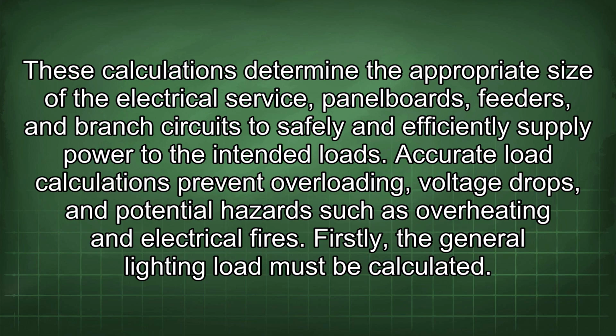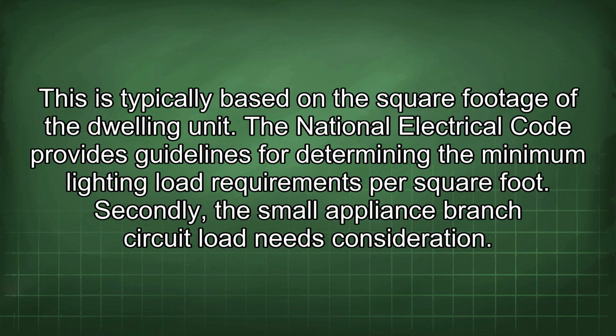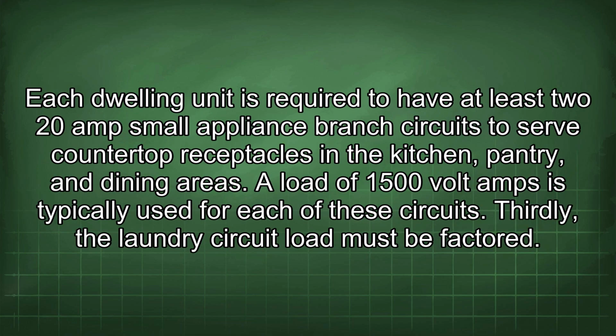Firstly, the general lighting load must be calculated. This is typically based on the square footage of the dwelling unit. The National Electrical Code provides guidelines for determining the minimum lighting load requirements per square foot. Secondly, the small appliance branch circuit load needs consideration. Each dwelling unit is required to have at least two 20-amp small appliance branch circuits to serve countertop receptacles in the kitchen, pantry, and dining areas. A load of 1500 volt-amps is typically used for each of these circuits.